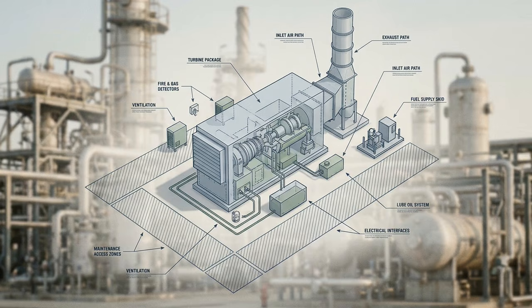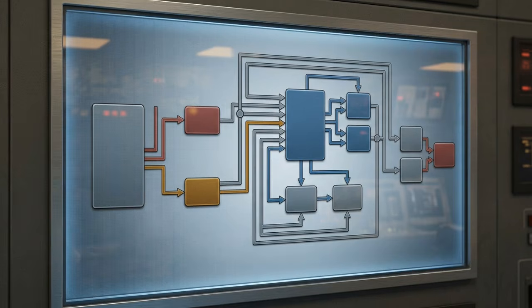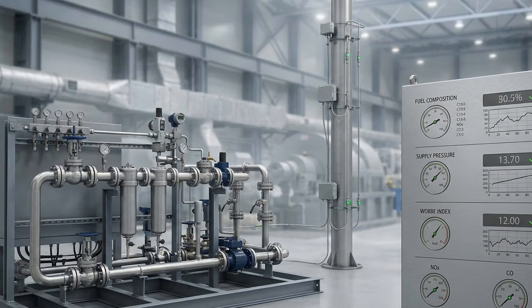Package integration can become the largest practical constraint. Foundation loads, footprint, inlet and exhaust systems, fuel supply, lube oil, electrical interfaces, ventilation, fire and gas systems, and maintenance access can all affect feasibility. Controls and safety systems also need a full interface review. Turbine control, compressor control, plant DCS, emergency shutdown, vibration monitoring, fire and gas detection, permissives, trips, and communications must be engineered as one protected system. Fuel and emissions are another major filter. Fuel composition, supply pressure, Wobbe index, contaminants, NOx, carbon monoxide, and local permitting requirements can determine whether a candidate turbine is practical for a specific site.